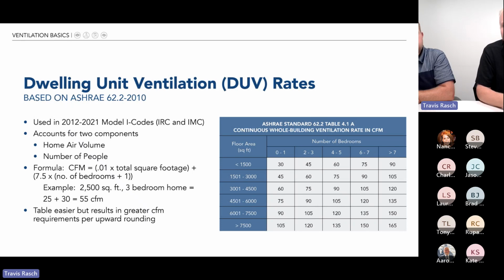So the formula they came up with is 1% of square footage and then 7.5 CFM per person. To estimate the number of people in a home, they use number of bedrooms plus one, figuring the master bedroom probably has 2 people in it, other bedrooms probably have 1. So a typical 3-bedroom home probably has 4 people. As an example, a 2,500 square foot 3-bedroom home: 1% of 2,500 is 25 CFM for that half of the equation. And then 7.5 times 4 is another 30. You add those together and that home would require 55 CFM.